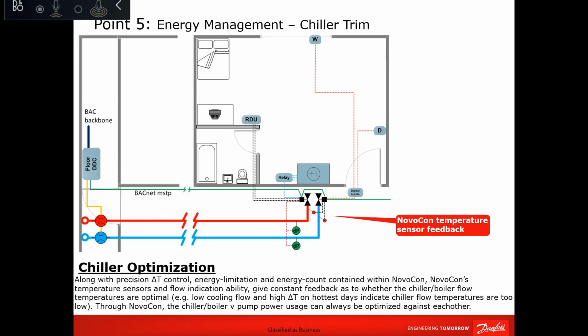Every area is connected, communicating with the Novocon. So the 5.5 can be 6.5, can be 7.5. It's based on the peak load condition, whether it is part load, full load, etc. So the temperature can be increased, and if you increase the supply temperature, you reduce the energy consumption of the chiller. How can you do that? Only by seeing the effect of increasing that temperature on the zones. You will end up with one position to trim the chiller to your most optimum supply temperature. And you know that half a degree in the supply will make a really big difference in the energy consumption.